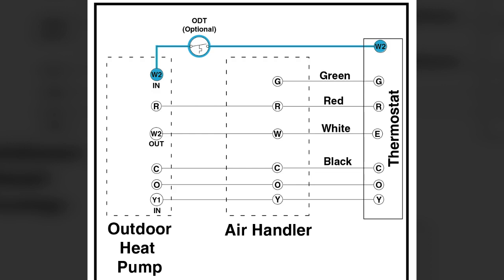If for some reason that heat pump is not keeping up, then we're going to go into W2 and energize that also. W2 is going to be either W2 or auxiliary. Some thermostats call it auxiliary, so keep that in mind also.